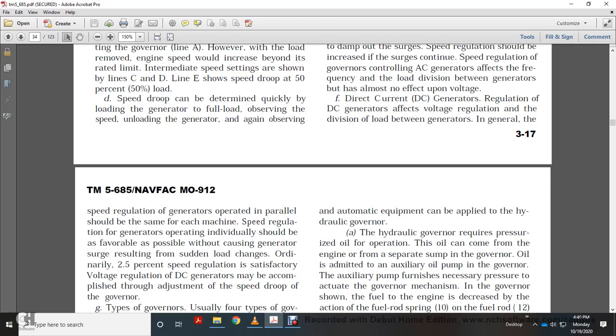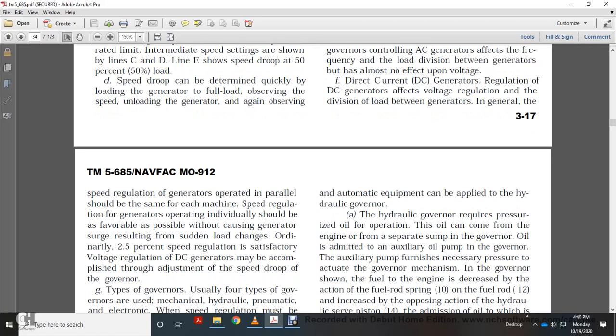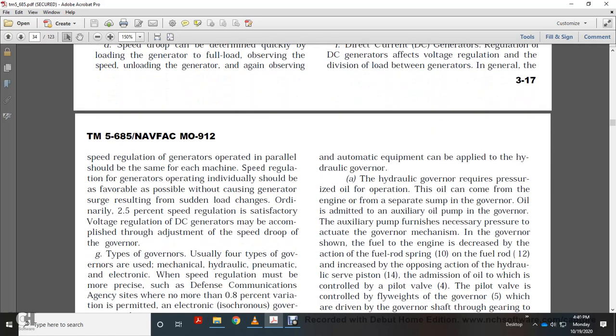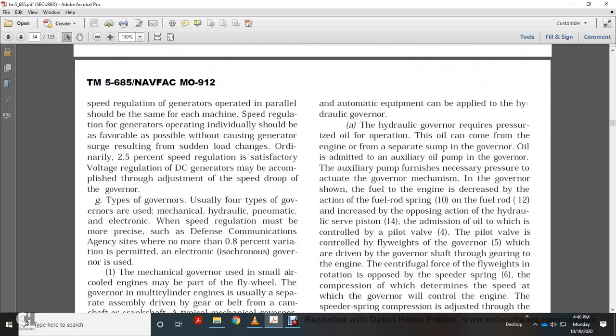For DC generators, speed regulation affects voltage regulation and the division of load between generators. The speed regulation of generators operating in parallel should be the same for each machine. Generators operating individually should have favorable speed regulation where possible, to avoid surging from sudden load changes. Ordinarily, 2.5% speed regulation is satisfactory. Voltage regulation of DC generators may be accomplished through adjustment of the speed droop of the governor.